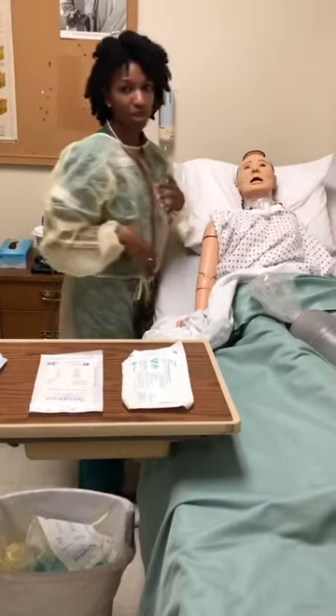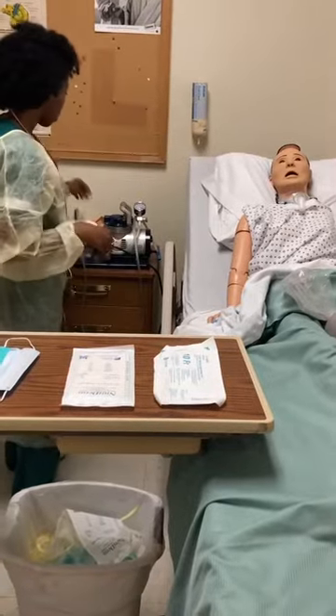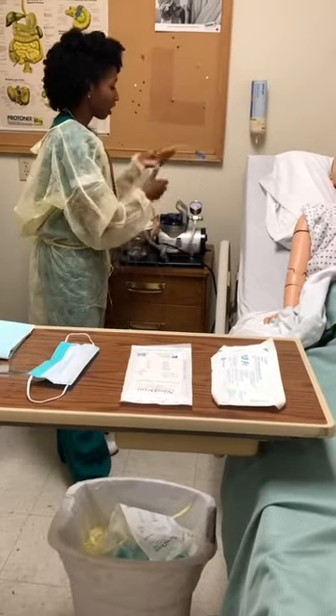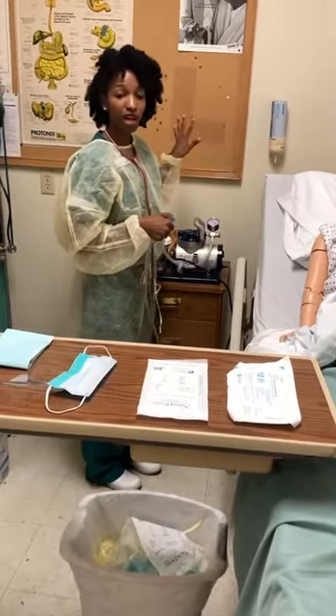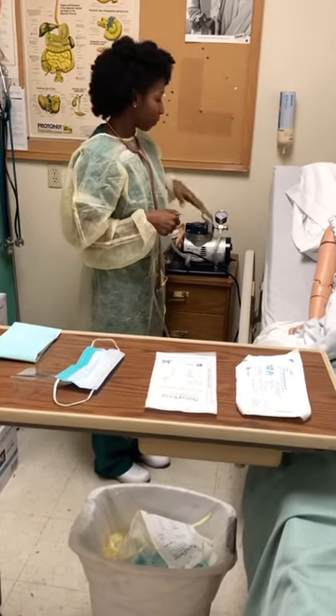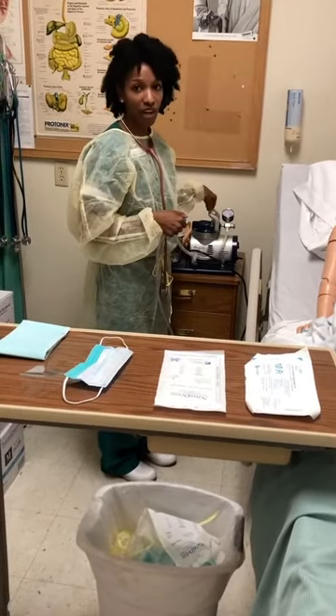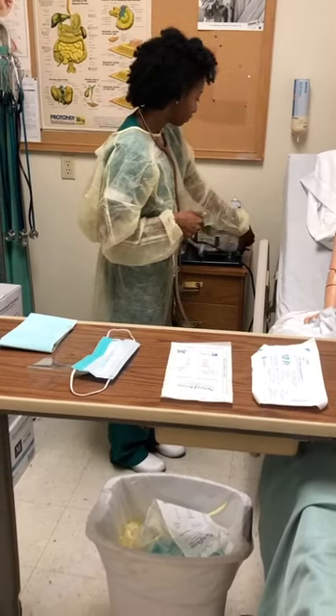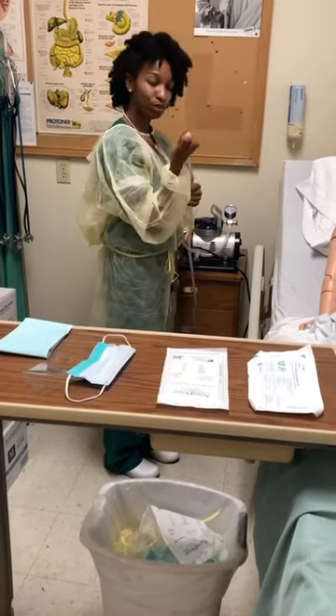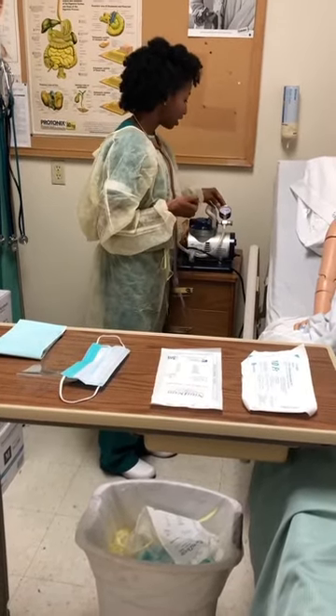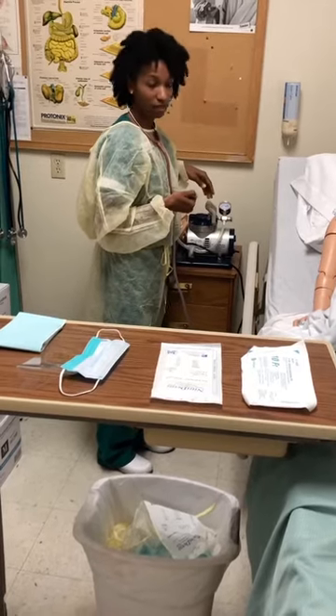Before I start, I want to test my equipment. I will grab my suction catheter. If it was a wall suction, it would be 120 to 150, but since we have a portable one, we want it to be 5 to 10. I'm going to turn it on. I'm going to occlude, and it is between 5 and 10.